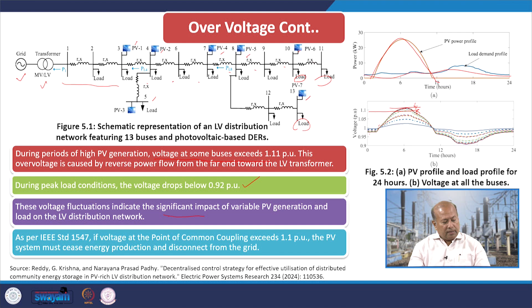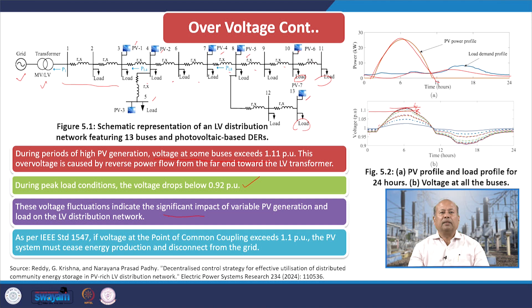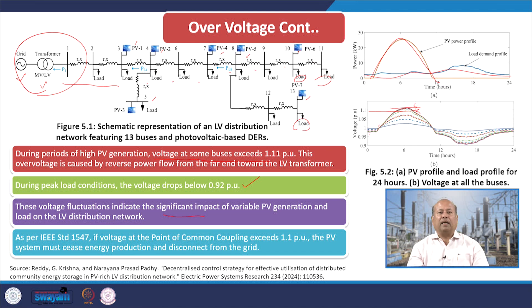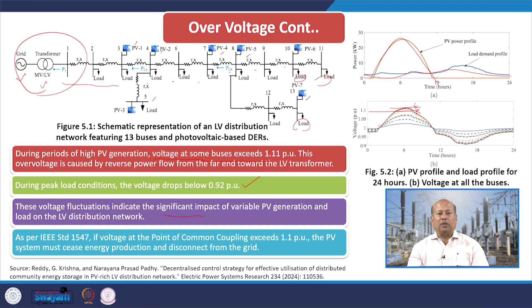As per IEEE standard 1547, if voltage at the point of common coupling exceeds 1.1 per unit, the PV system must cease energy production and disconnect from the grid. So at the PCC, if the voltage is more than 1.1 per unit, we have to de-rate or curtail generation from the PV — that is a strict guideline. It is therefore very important to plan properly how, where and what amount of PV to be integrated so that de-rating or curtailment in PV generation does not take place.